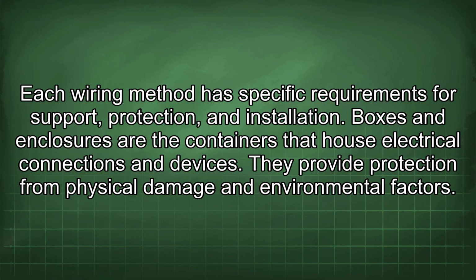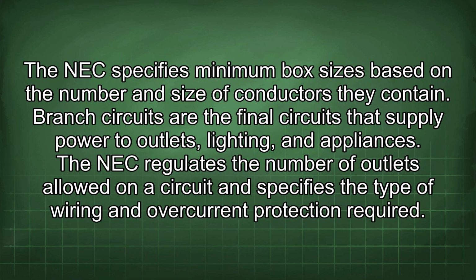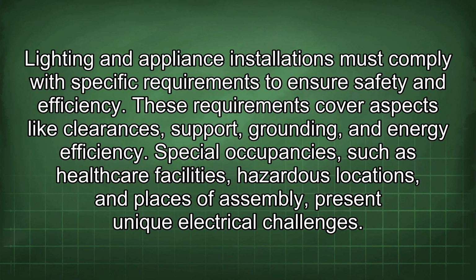Boxes and enclosures are the containers that house electrical connections and devices. They provide protection from physical damage and environmental factors. The NEC specifies minimum box sizes based on the number and size of conductors they contain. Branch circuits are the final circuits that supply power to outlets, lighting, and appliances. The NEC regulates the number of outlets allowed on a circuit and specifies the type of wiring and overcurrent protection required. Lighting and appliance installations must comply with specific requirements to ensure safety and efficiency.